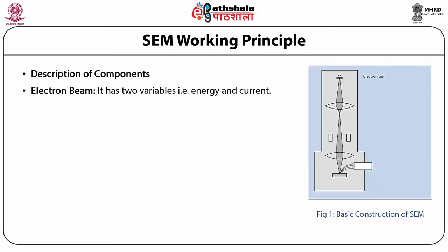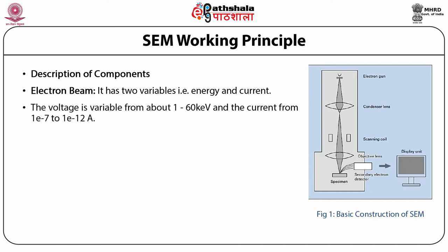Let us now describe each component of SEM. First is the electron beam, which has two variables: energy and current. The voltage is variable from about 1 to 60 kilo electron volts, and the current from 1×10⁻⁷ to 10⁻¹² amperes. These values are specific to the instrument model.